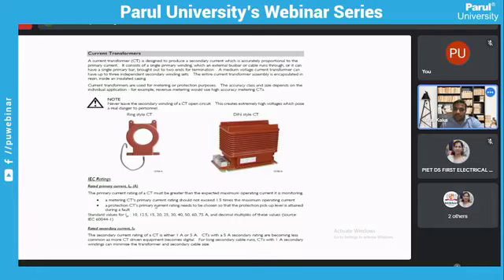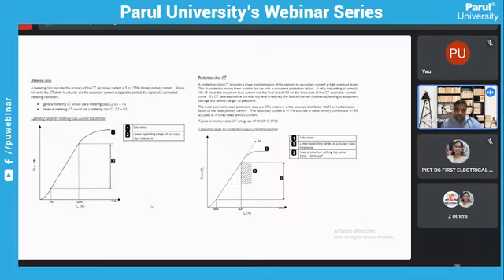So we need to design a CT keeping its short circuit level also into consideration. Again, this is just an overall view in terms of metering as well as protection class CT. General metering class we would normally use from class 0.5 to 1, but the revenue metering class will be slightly with a higher accuracy of class 0.2 to 0.5.